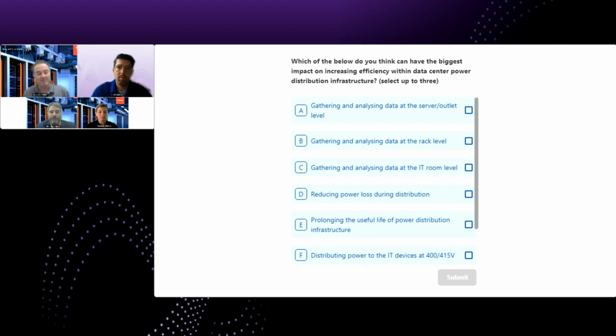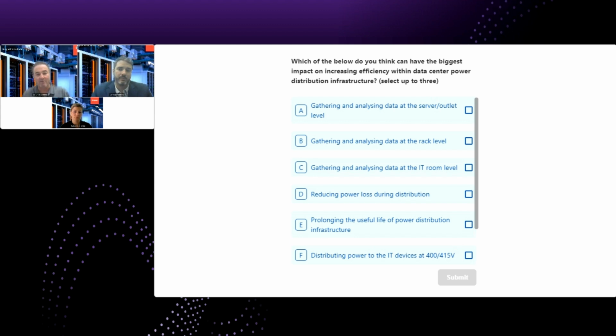One thing that's not often talked about in a data center is the fact that we've got a ton of switch mode power supplies, and we know these generate harmonics. That's seen in the data center in a number of ways: it may be higher power supply failures within the servers, inefficiencies in the power factor—harmonic power factor. You can see how much power is actually being used on the devices and how much is being wasted.